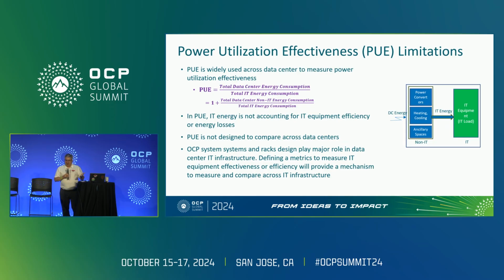I was told there would be no math, but the basics are that it's a one-based coefficient - you're trying to get down to 1.0. What it shows is effectively the amount of power consumed in total by the data center divided by the power that goes to running the IT workload. So if 100% of the power in the data center was consumed by the IT workload, that would be a 1.0 maximum PUE.